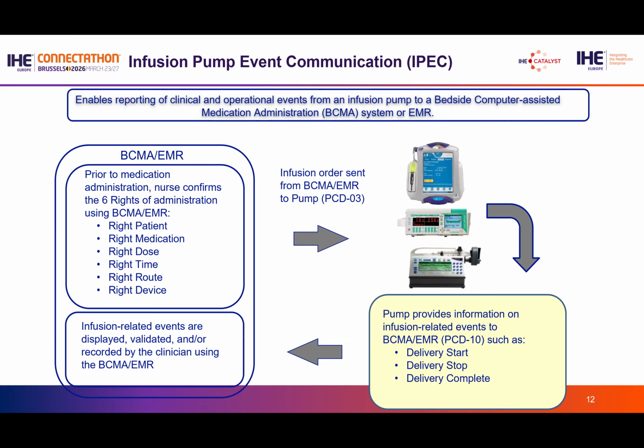Within the Connectathon in Gazelle, there are 7 IPEC tests defined. There's a basic test that is required for all devices, all pumps, and the other 6 are optional based on either the pump type or supported features. Doing things like piggyback infusions or channel relay or PCA type pumps. And depending on which pump type you've got, you may have to do more tests than just the one basic one. But everybody has to do the one basic one.